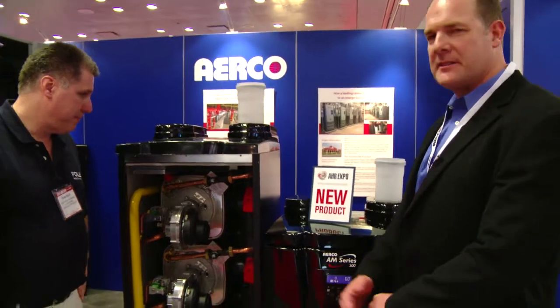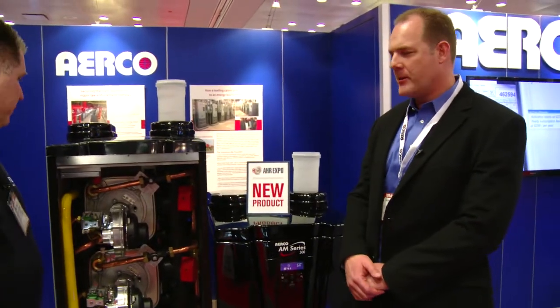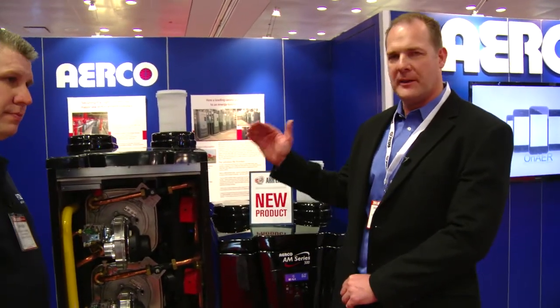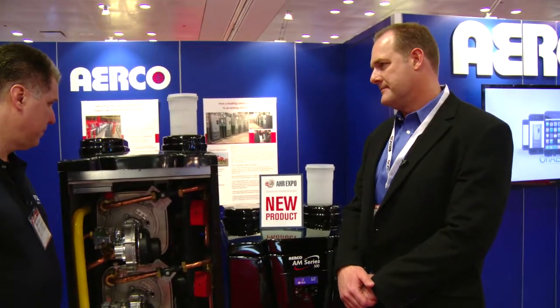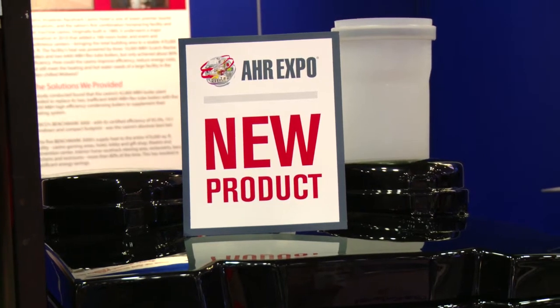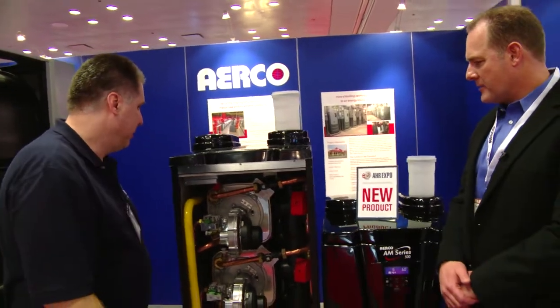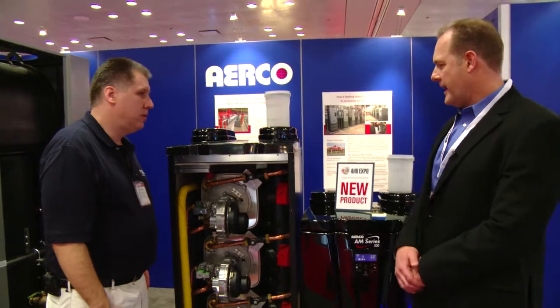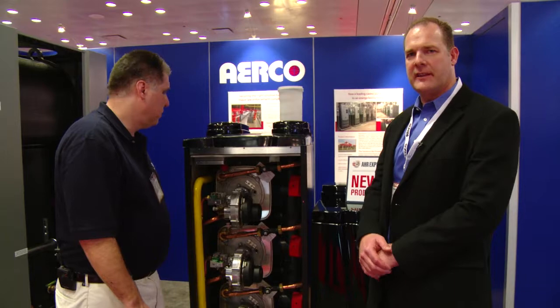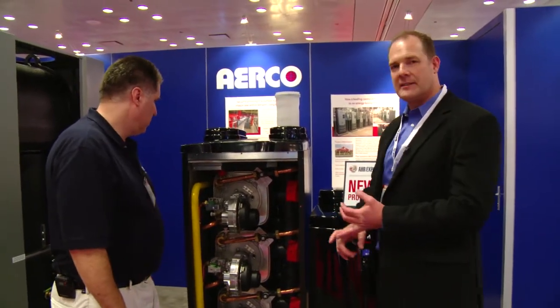Harold, we got a new product here. I didn't see this one before. Yeah, this is a new introduction for AERCO called the AM series, both boiler and water heater. This product really fills in a gap for AERCO in that it takes both our water heating products as well as our boiler products from 1 million BTU input all the way down to 399,000 BTU input. Looks like it's in a nice compact chassis. We can get it into a lot of tight boiler rooms. Yeah, it was designed for ease of installation, as well as it's a high efficiency product. It's a water tube stainless steel heat exchanger that gives you high efficiencies, as well as high turn down.